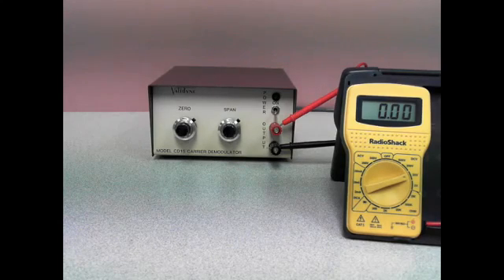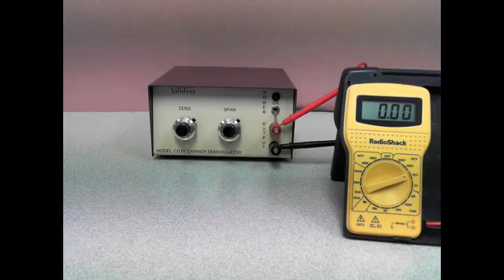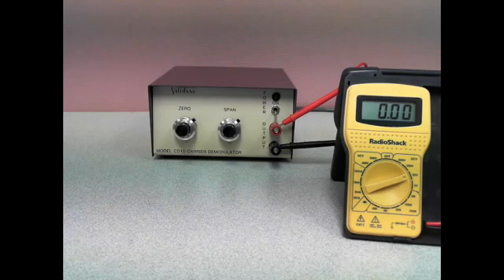If the CD15 has been calibrated with the sensor, write down the dial readings on the zero and span adjustments so that these can be reset later.